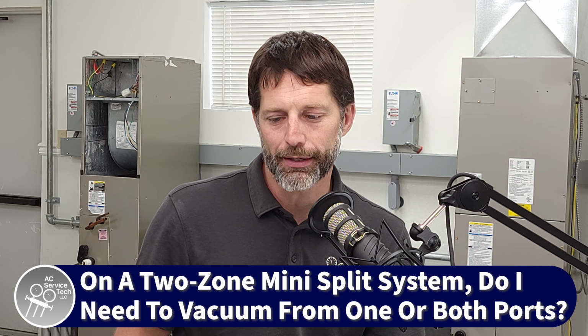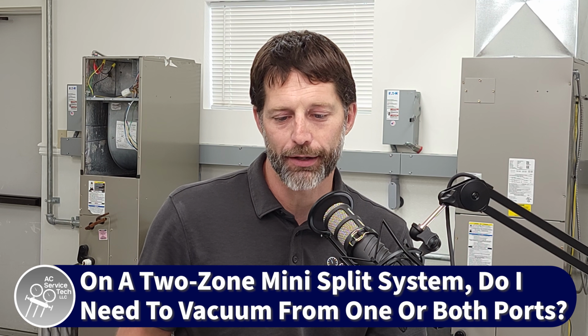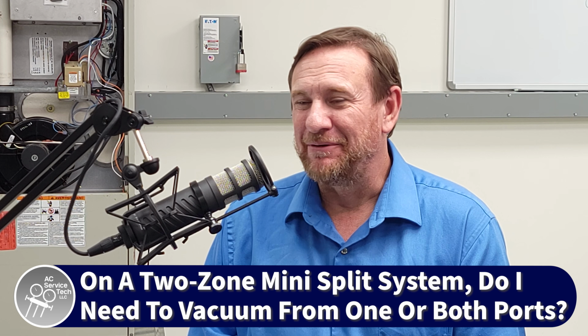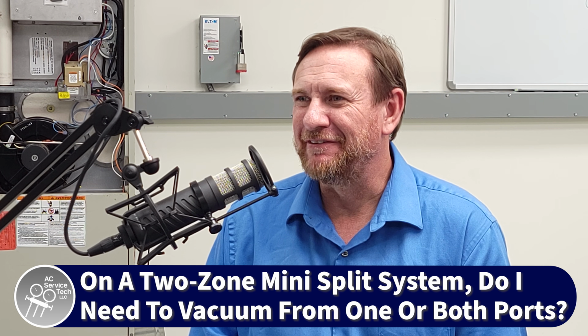Absolutely right. Another technician named Fred asks, on a mini split dual zone system, do I need to vacuum both vapor port sides or just one? I would say both, but there's so many different varieties out there. Everyone that I've seen, we're going to have to actually recover all that refrigerant out and weigh it back in and know our charge is right. However, I have seen some of the Mitsubishi brands in particular that have individual valves at the indoor unit and the outdoor unit that allow you to isolate that one particular section. So it would depend on the brand and also the installation, in my opinion.